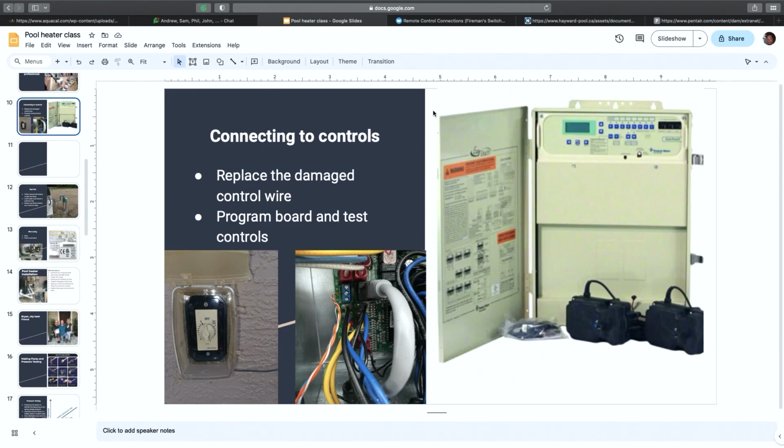So I wanted to first talk about a really common service call that we're going to get this year, which is pool heater's not working in a vacation rental. The most common complaint from a guest is that when they went to turn on spa mode, either the spa didn't get hot or it stayed in pool mode. So when you come out and look at the pool heater, everything's running great. I don't see any issue here, probably something going on with the guest. And then you leave, and you likely haven't addressed the issue.